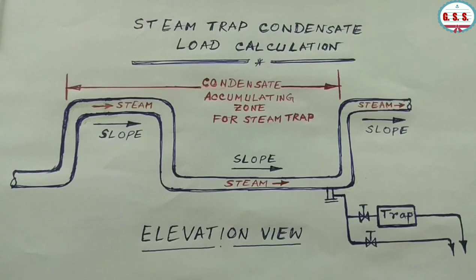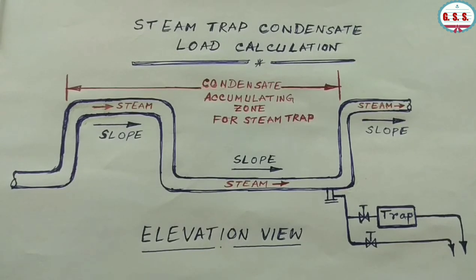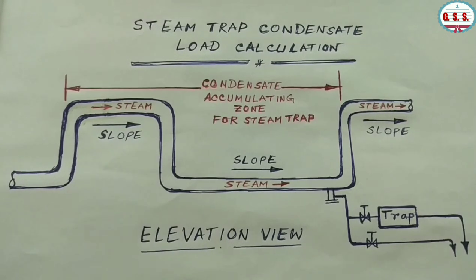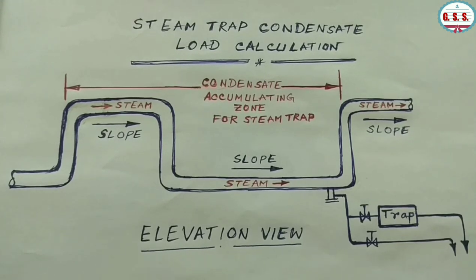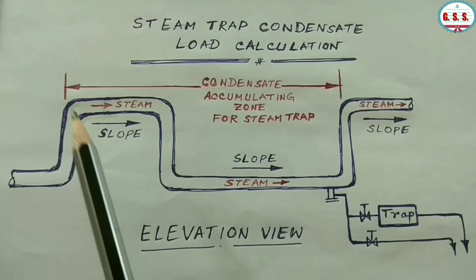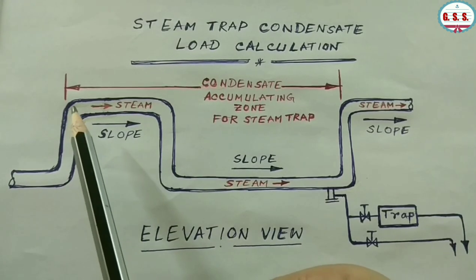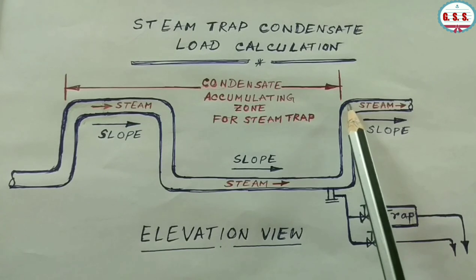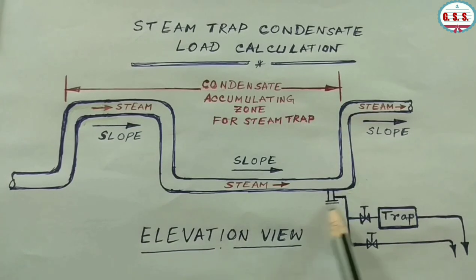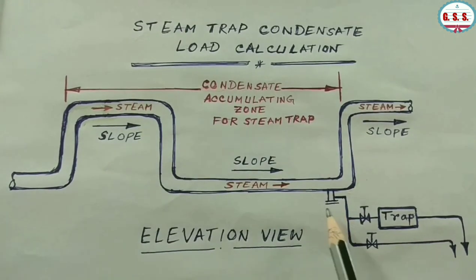In this elevation view, a steam line is shown. Since the steam line has a slope along the flow, in this piping configuration, the condensate accumulating zone is from the left side top bend to the right side top bend, and the location of the trap is close to the lower bend.